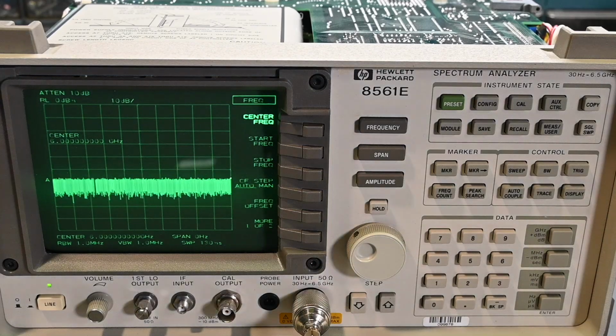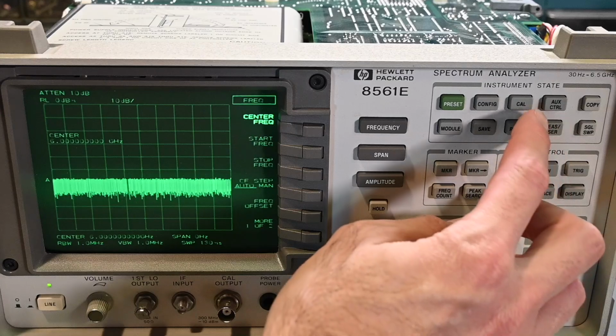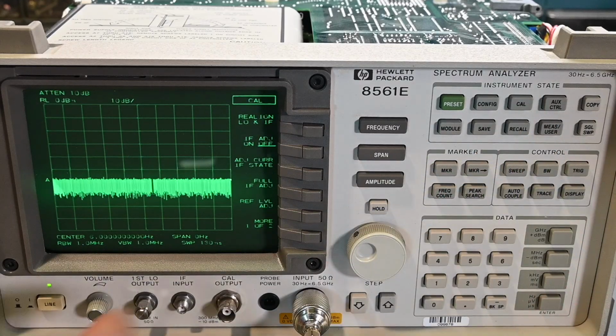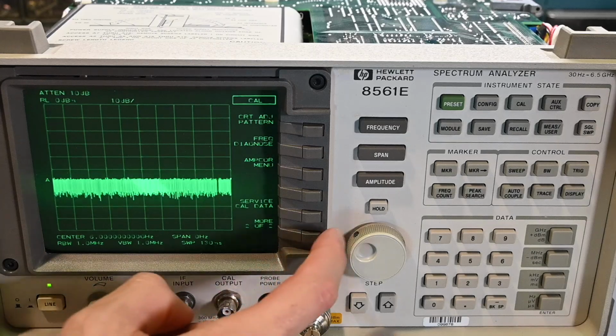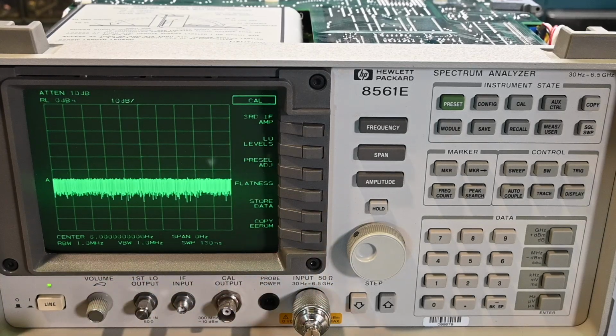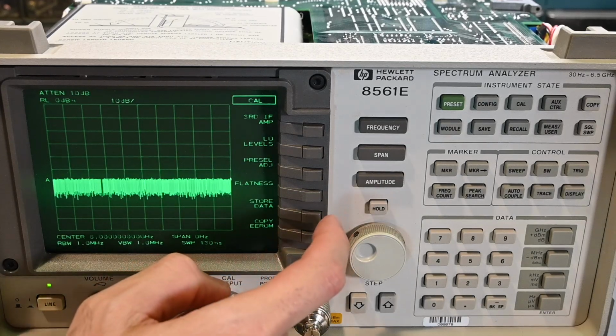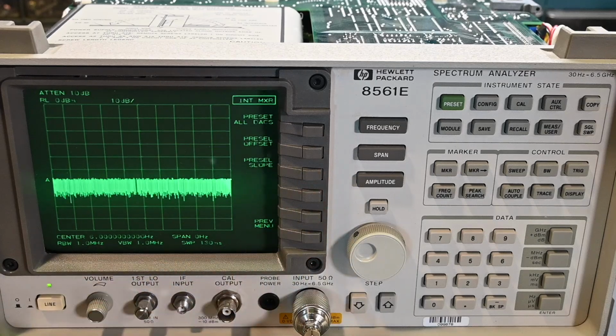Okay, there we go, 6 gigahertz, and then the offset, so I'm compensating for the loss in the cable. Okay, so now it says to press cal, more 1 of 2, service cal data, pre-select adjust, pre-select offset.